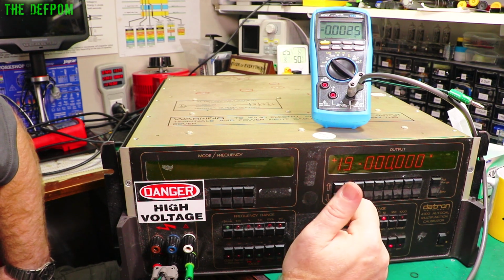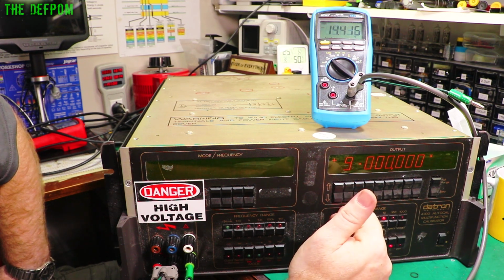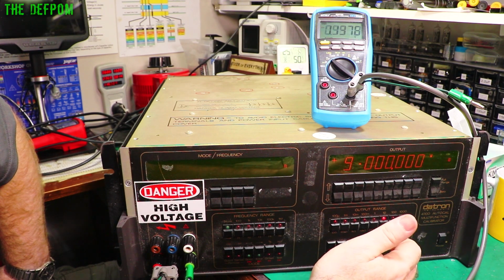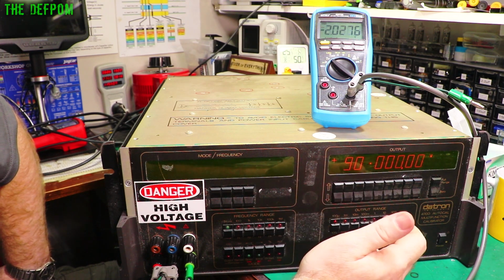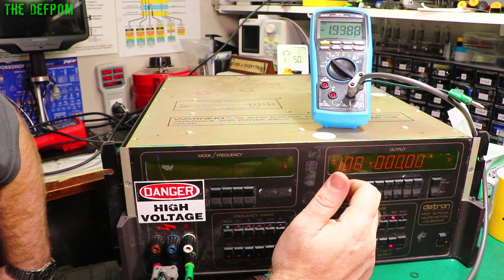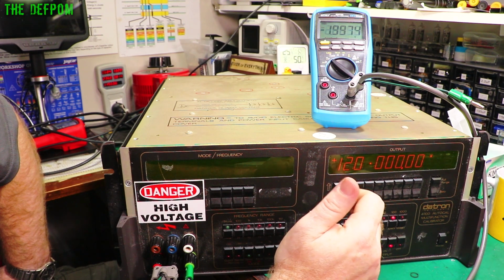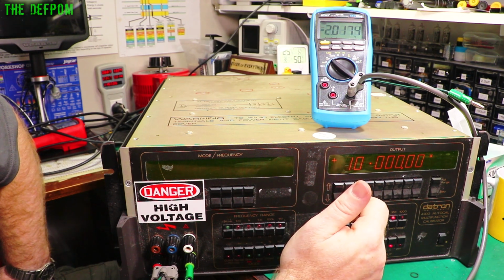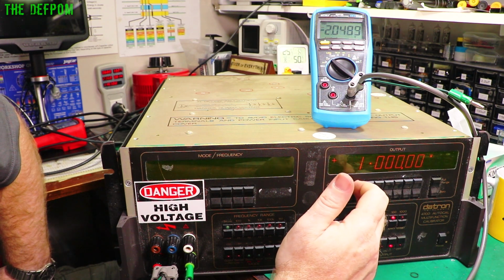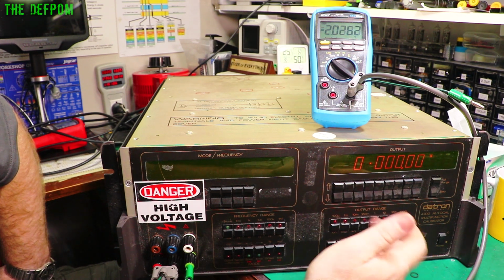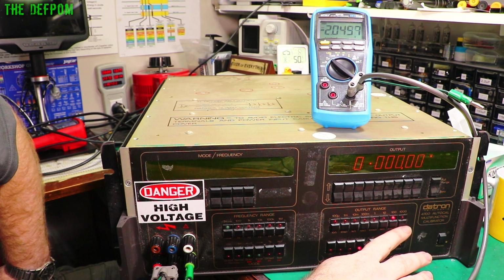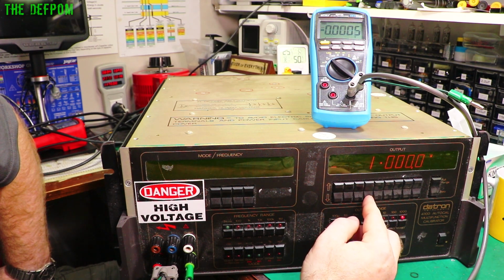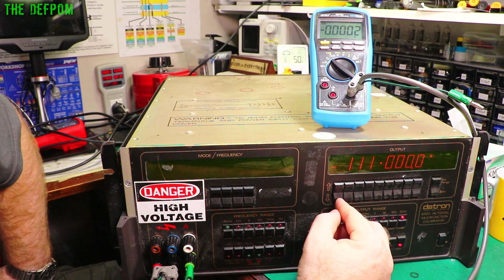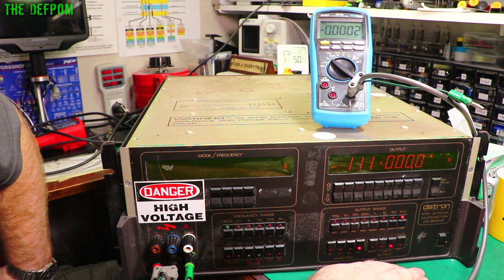Back to 10 volt range. Turn it down to 9 volts to 100 volt range. There's no errors. I'm getting minus 2 volts. So something's definitely very wrong there. So the high voltage range isn't working. Okay, let's try the 1000 volt range. That also is not working. Oh, range is off.